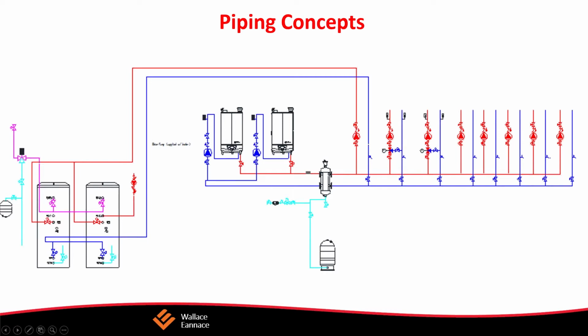A better alternative is a monoflow T system. You'll have a tendency to get equal delta T. The water temperature stays constant, and it's much easier to zone and control because you're continuing to flow water through there. And the monoflow T, also known as a Venturi T, how does that work? Essentially, as you can see from this diagram, there's a Venturi on one end. The flow goes through there, and it creates a pressure differential, allowing the water to come out of the radiator.